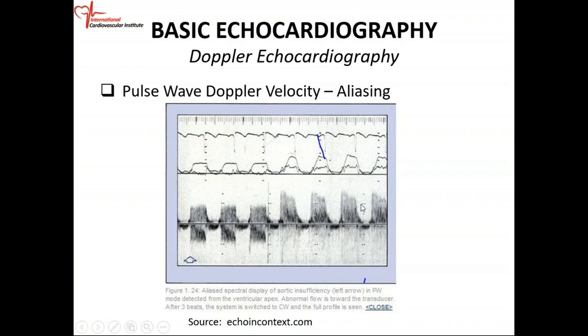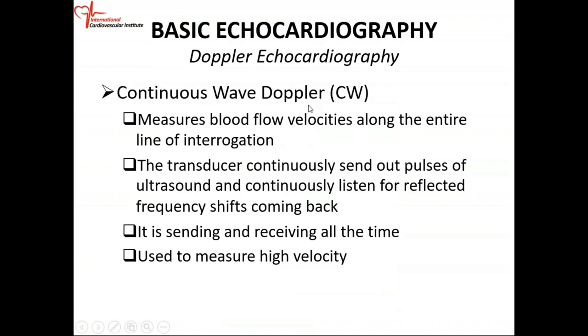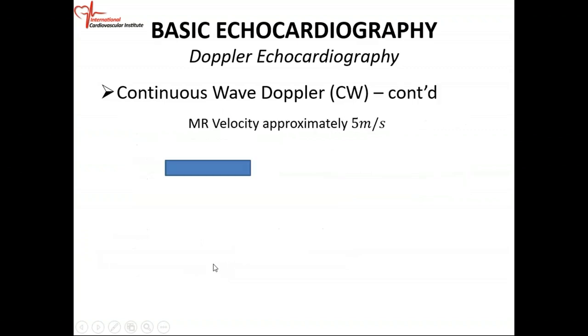You have to switch to what we call continuous wave Doppler. Continuous wave Doppler measures blood flow velocity along the entire line of interrogation. The transducer is constantly sending out impulse and constantly listening or receiving. Whereas with pulse wave Doppler, it sends out an impulse and then waits for the return signal — continuous wave does not do that. It's continuously sending out impulse and continuously receiving reflected frequencies. Because of this, you can measure high velocities — it's sending and receiving at all times.